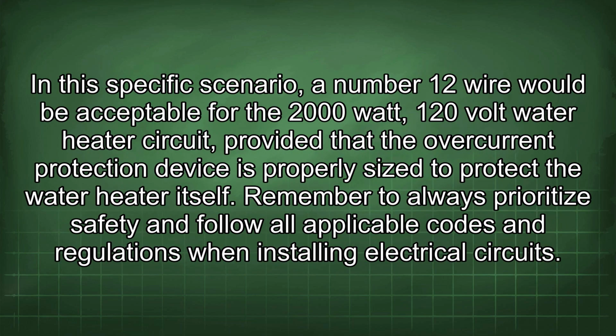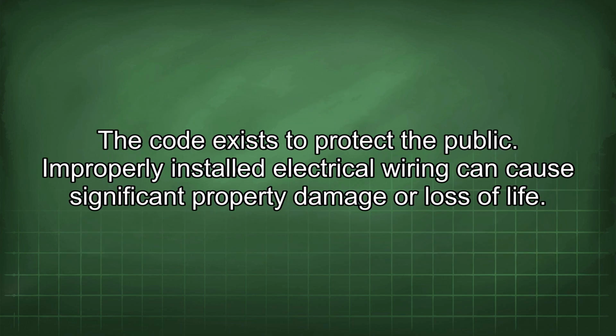In this specific scenario, a number 12 wire would be acceptable for the 2000 watt, 120 volt water heater circuit, provided that the overcurrent protection device is properly sized to protect the water heater itself. Remember to always prioritize safety and follow all applicable codes and regulations when installing electrical circuits. The code exists to protect the public. Improperly installed electrical wiring can cause significant property damage or loss of life.